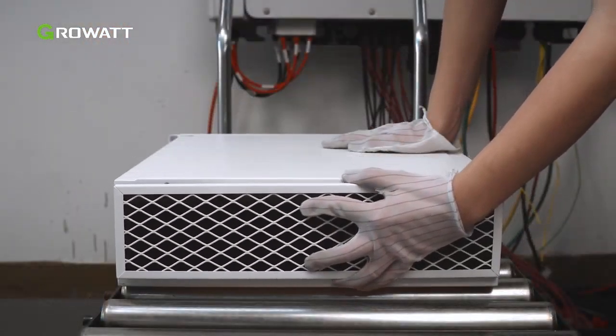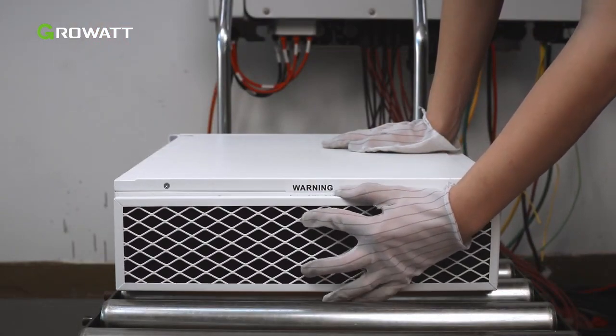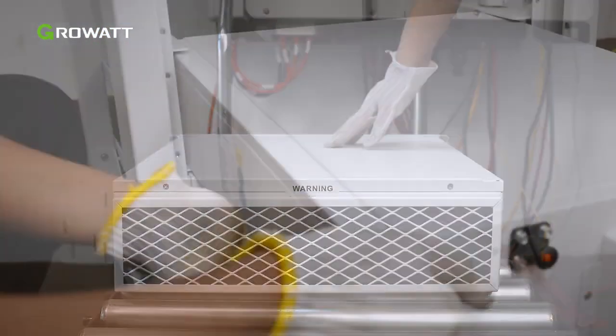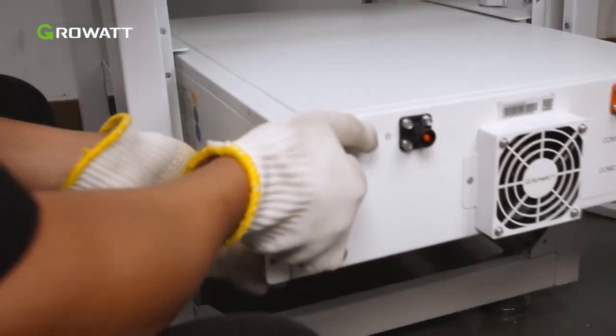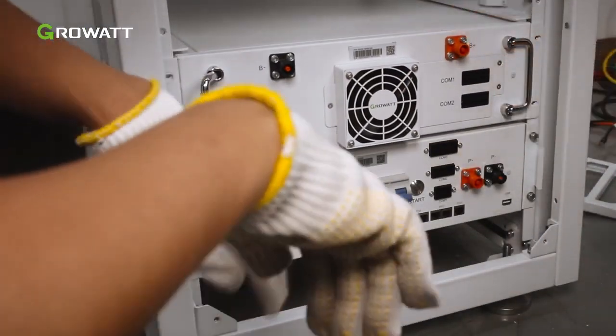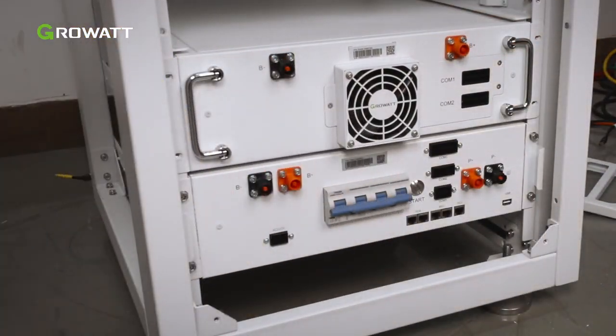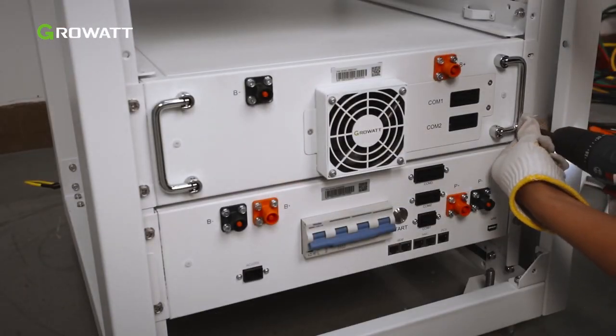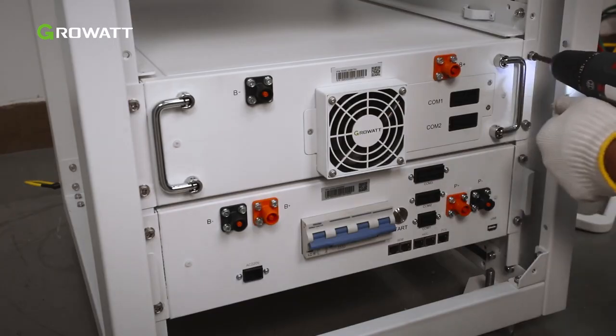Install a dust-proof net behind the battery module each time before installation. Lift the battery module to the height of the corresponding slot with a lifting trolley, then push the battery module into the rack. Tighten the screws to secure each battery module after it has been installed in the rack.